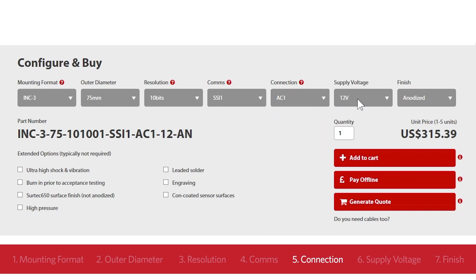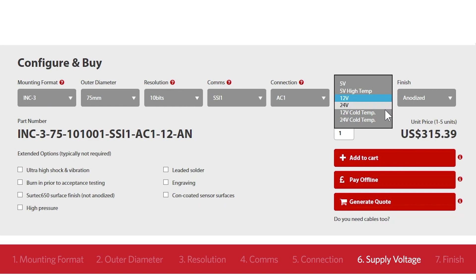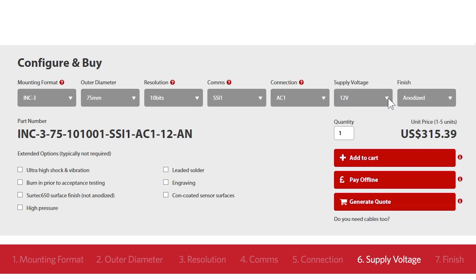The next element is supply voltage. For operating environments with temperatures up to 105 Celsius, select the 5HT option. For low temperature applications down to minus 60, choose the 12CT or 24CT options. For analog voltage output, you'll need a 12 or 24 volt supply. In this example, we'll choose the most common supply, which is 12 volts, which actually covers a range of 4.5 to 32 volt DC supply.